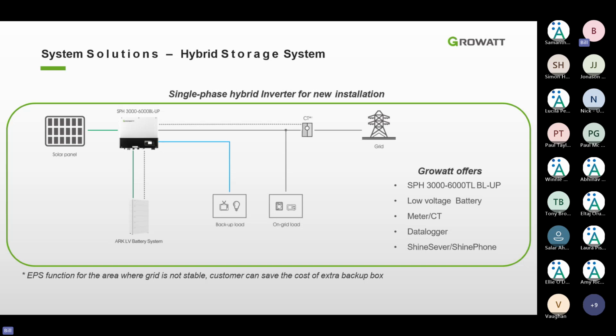Normally it comes with a CT for the communication, but now since the grid DNO is asking for G100 regulation, as long as your local DNO asks for that, just remember to use a meter instead of just a CT, because our Growatt meter is suitable for all G100 situations. So just be careful and enable the export limiting function, which is on your inverters, or you can use our app to turn this on.